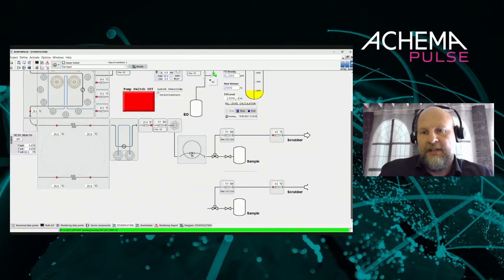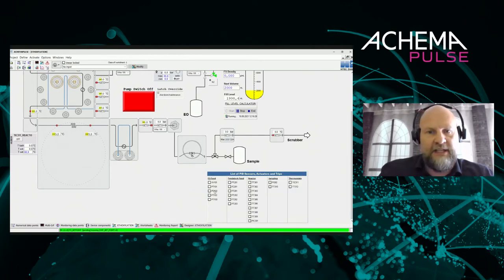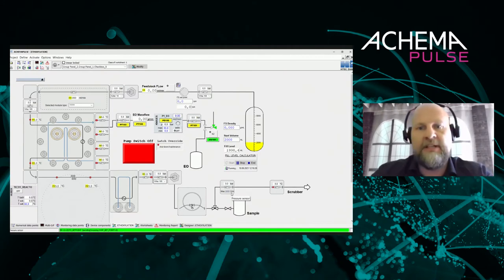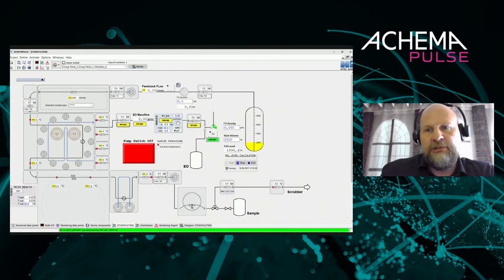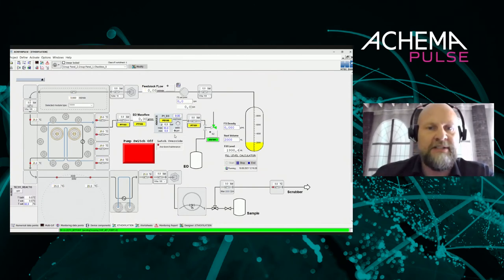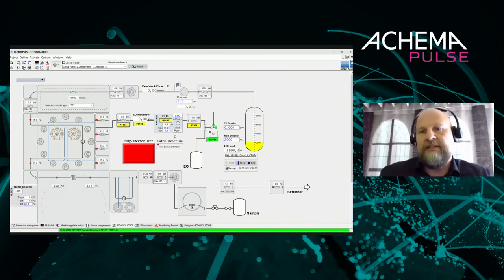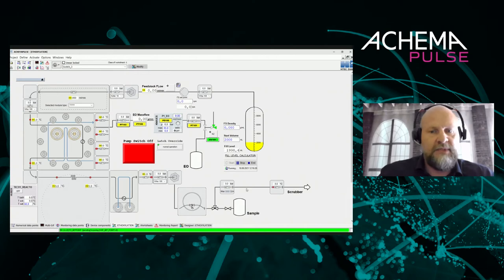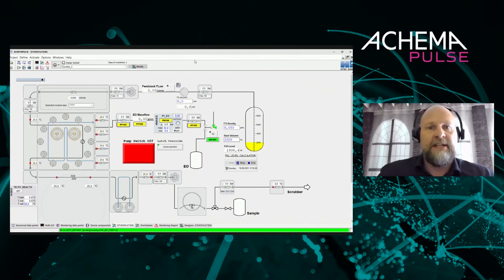In this project we also added color-coded labels to identify measuring points with the P&ID. Green means everything is okay, yellow means the defined operating conditions are not met, and red means there is a problem — which also triggers an acoustic warning to the operator that something is not right.